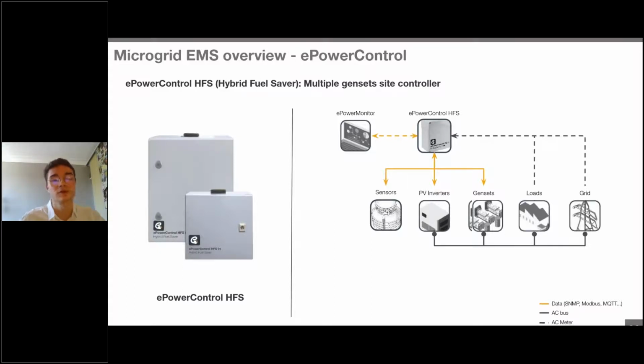But we will talk about the ePowerControl HFS. The ePowerControl HFS is the Elum product that will be able to manage multiple genset sites. It of course ensures the data logging, connected to the ePower Monitor platform cloud services thanks to VPN access and internet connection. But it is also physically connected on site to different sensors. If you have, for example, some performance ratio to be calculated, we can integrate any monitoring weather station or any system that needs to be monitored. And of course, we have this connection with the PV inverters, so when we're working with Fronius, we connect directly to the data manager and communicate over Modbus with the equipment to control the PV inverters at any time.